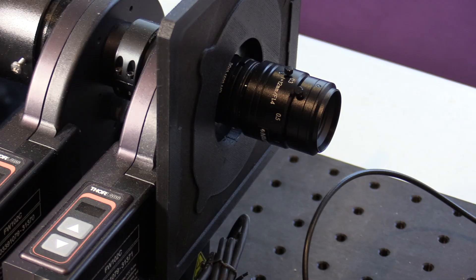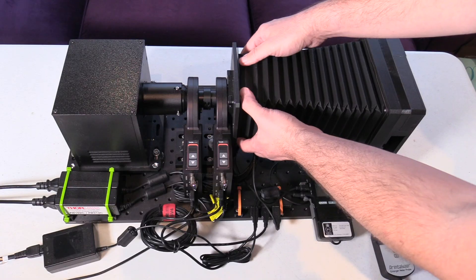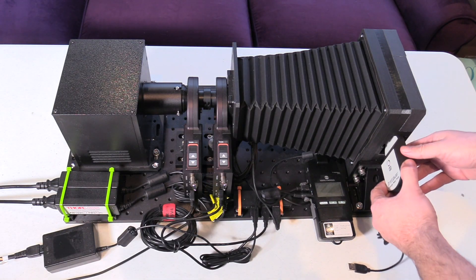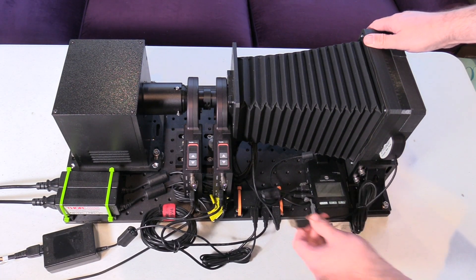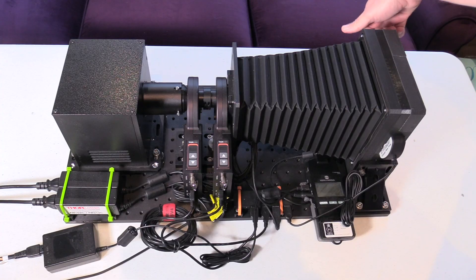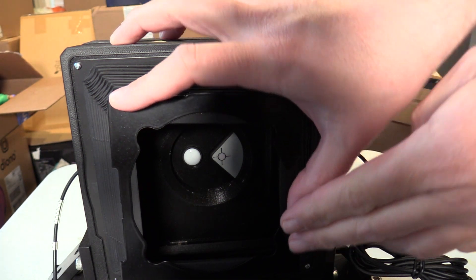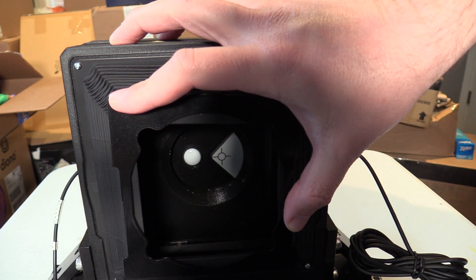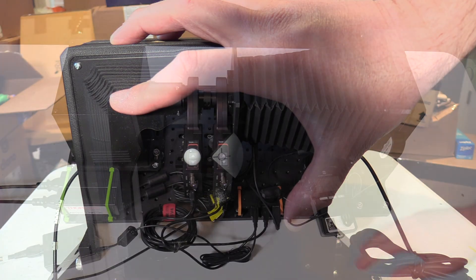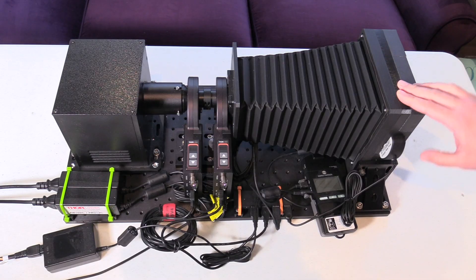And between the lens and the measurement plane, I have this repurposed camera bellows to block out stray light. The way this works is the meter probe gets inserted back here, and there's also a sensor probe in here from this calibrated lux meter. The light source shines light through, and a piece of computer software controls the whole thing, cycling through various filters and various sensor modes to perform the entire calibration process for the meter probe.